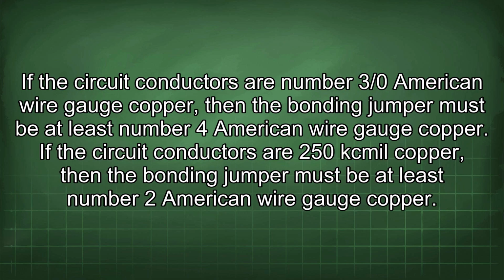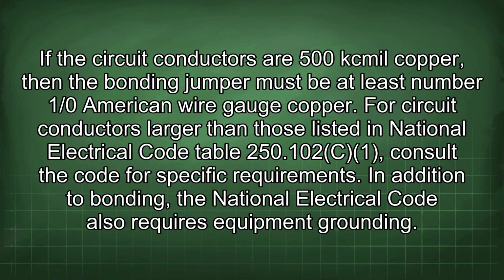If the circuit conductors are number 3/0 American wire gauge copper, then the bonding jumper must be at least number 4 American wire gauge copper. If the circuit conductors are 250 kcmil copper, then the bonding jumper must be at least number 2 American wire gauge copper. If the circuit conductors are 500 kcmil copper, then the bonding jumper must be at least number 1/0 American wire gauge copper. For circuit conductors larger than those listed in National Electrical Code Table 250.102, consult the code for specific requirements.